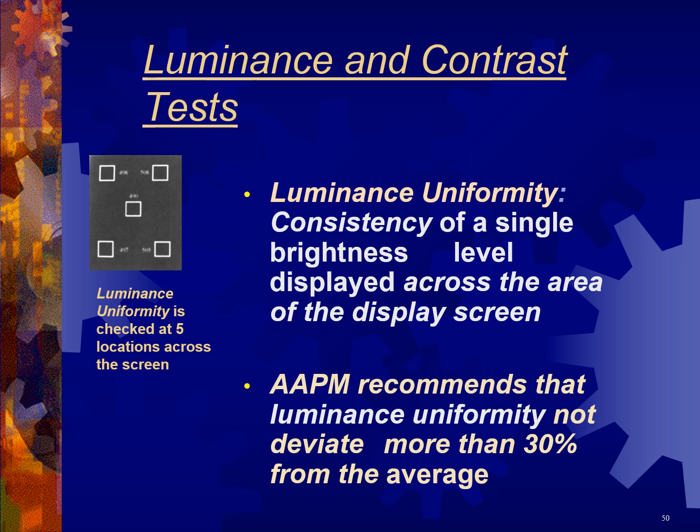For the uniformity test, the maximum deviation is... So if you know the monitor is supposed to be broadcasting a singular color, the luminance should be measuring the same at every location of the monitor. Anything greater than 30% variance is considered non-uniform, and the monitor needs to be adjusted or replaced.